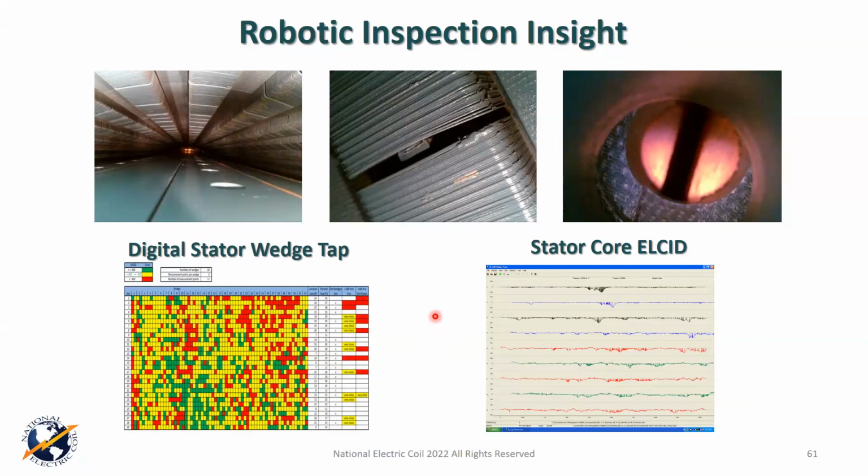And the cost of this robotic inspection is not tremendously expensive. It can range anywhere from maybe 45, 50,000 for all of this to as much as maybe 100,000, depending on the unit, the size, the number you're doing, when you're doing it, and all the different things. But that gives you at least some kind of framework as a range, all right? Not terribly expensive. Why would you waste that when you know that you've got problems? Pull the dang rotor and deal with the problem, okay?